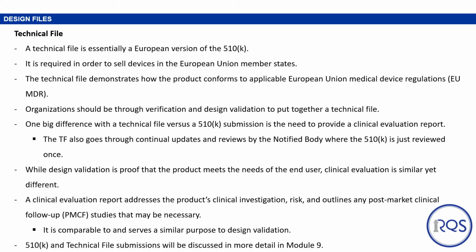A technical file is essentially a European version of the 510(k). It is required in order to sell devices in the European member states. The technical file demonstrates how the product conforms to applicable European Union medical device regulations, also known as EU MDR. Organizations should be through verification and validation to put together a technical file. One big difference with a technical file versus a 510(k) submission is the need to provide a clinical evaluation report. The technical file also goes through continual updates and reviews by notified bodies, where the 510(k) is just reviewed once.